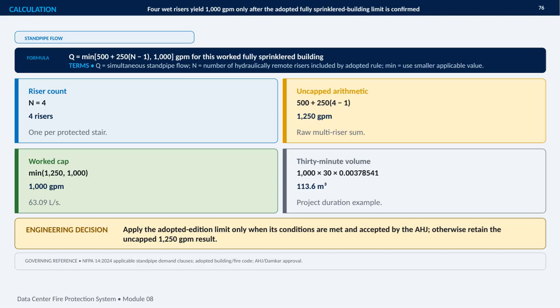This slide works through the standpipe flow calculation for a fully sprinklered building with 4 protected stairs, and the key point is that the final demand depends on the adopted rule and its conditions. The formula starts with 500 gallons per minute, then adds 250 for each additional hydraulically remote riser, up to the applicable limit. With n equal to 4, the uncapped calculation is 500 plus 250 times 3, which produces 1,250 gallons per minute. For this worked example, the fully sprinklered building limit is confirmed, so we use the smaller of 1,250 and 1,000. The governing simultaneous standpipe flow is therefore 1,000 gallons per minute, or 63.09 liters per second. Over a 30-minute duration, that flow represents approximately 113.6 cubic meters of water.